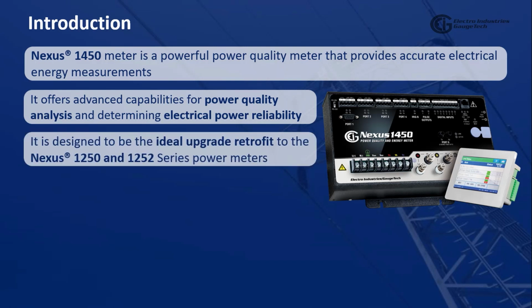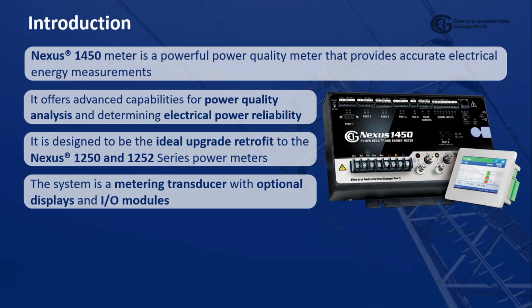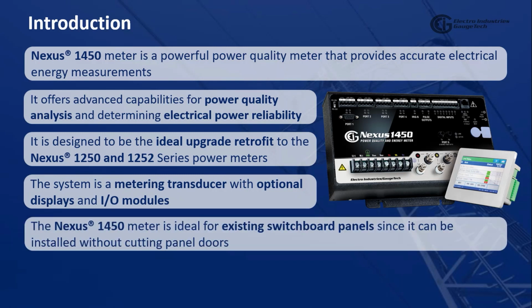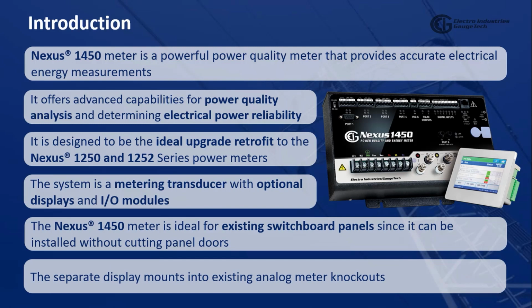It is designed to be the ideal upgrade retrofit to the Nexus 1250 and 1252 series power meters. The system is a metering transducer with optional displays and I/O modules. The meter is ideal for existing switchboard panels since it can be installed without cutting panel doors. The separate display mounts into existing analog meter knockouts.